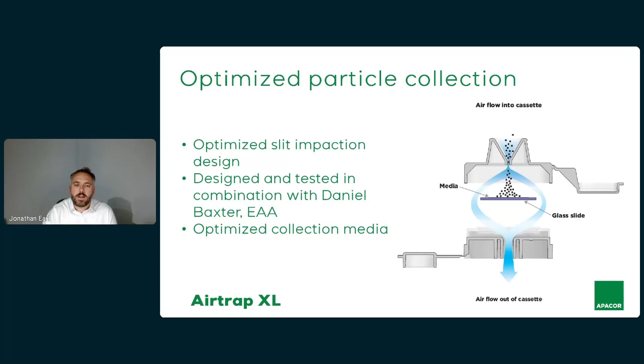These small black dots represent the airborne particulates, which you can see come through this optimized slit design that we've been working on with Dan Baxter. It's based off a Venturi inlet design, so the particles are drawn through and accelerated towards the glass slide and this collection media that we've been optimizing. We feel that means we get just the optimal collection of all the different airborne particles that may be of interest, from the smaller end of the scale right through to the larger end of the scale. We feel that we collect the best representation of particulates during that test.